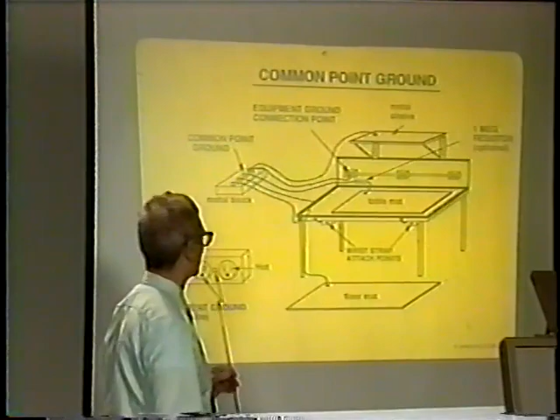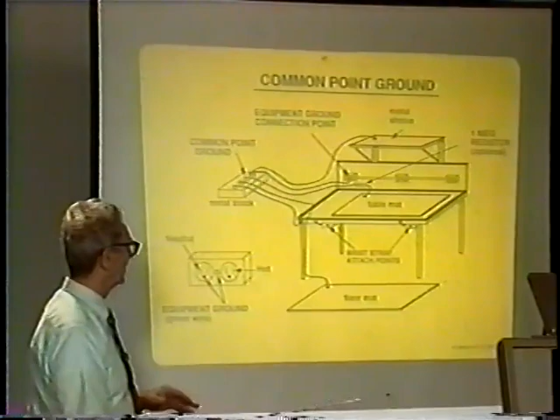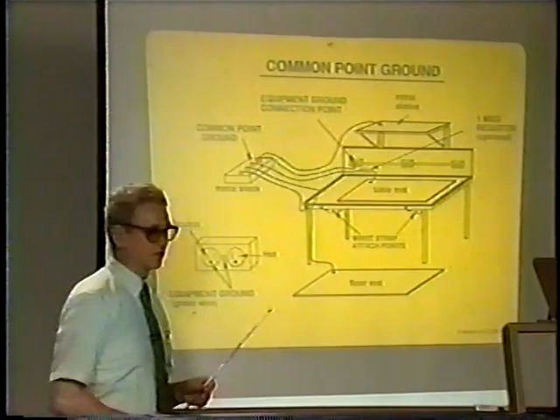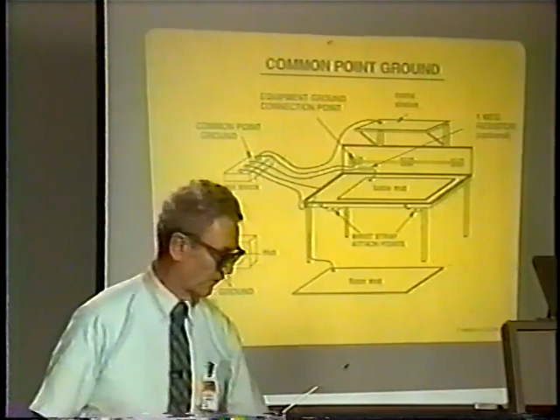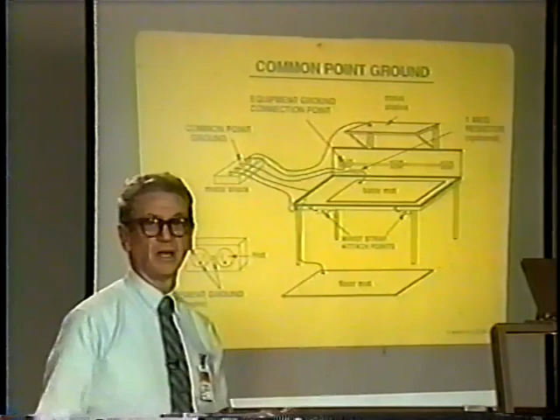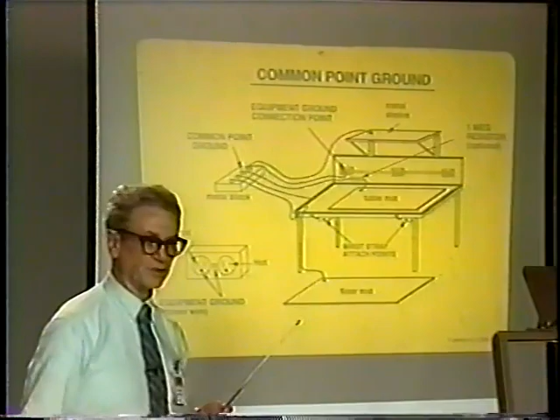The wrist strap connections here go to this point, and all that is connected to the equipment grounding conductor, which is connected to the building. The floor mat here is connected to that point. The only thing that isn't connected is the ESD floor, which is connected to the equipment grounding conductor through the building connection. This equipment grounding conductor is at the same potential as the building ground, so you do not have potential differences between any of these objects or pieces of equipment if they're all connected up and certified.